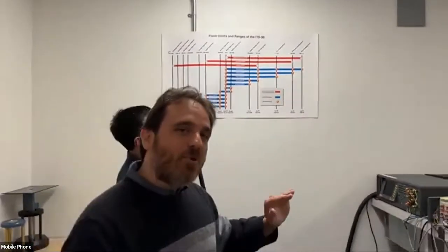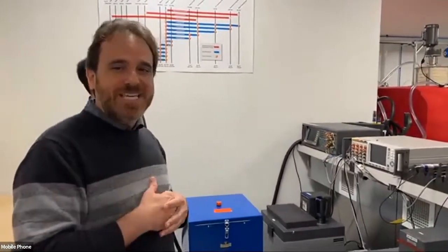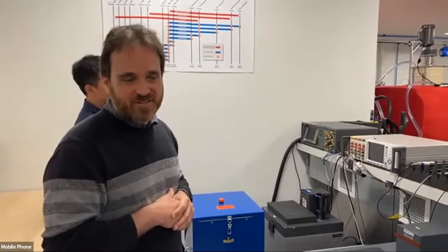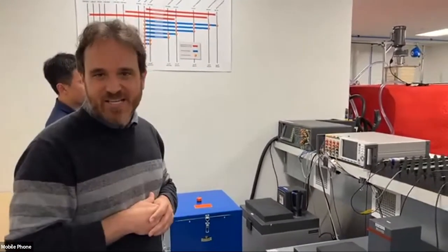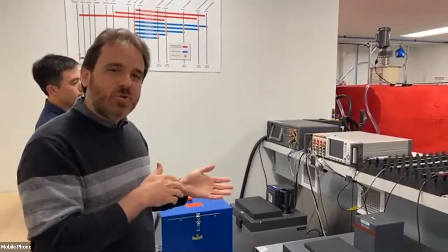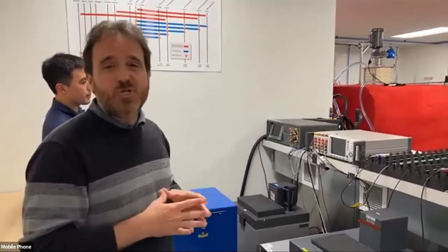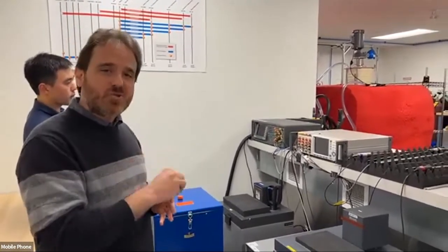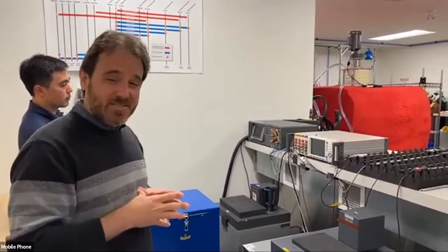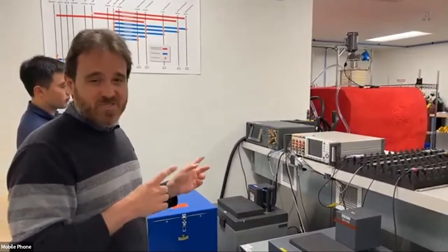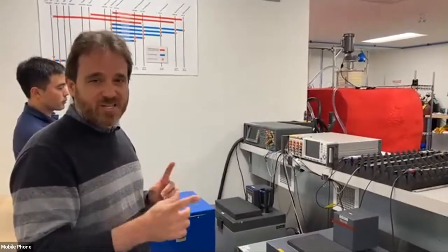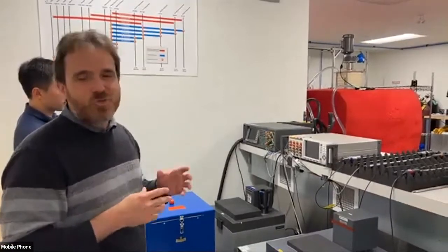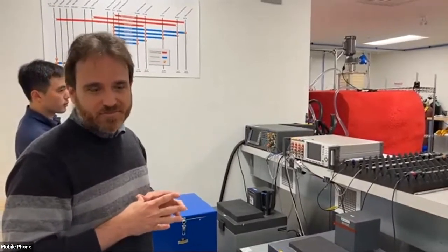And then for the upper limit, we use the gallium melting point. So we also have a gallium cell for that. And we actually do a verification in the triple point of water cell on a daily basis. We actually have 2 triple point cells, so we're constantly verifying in both cells. And we do the gallium verification once a month.